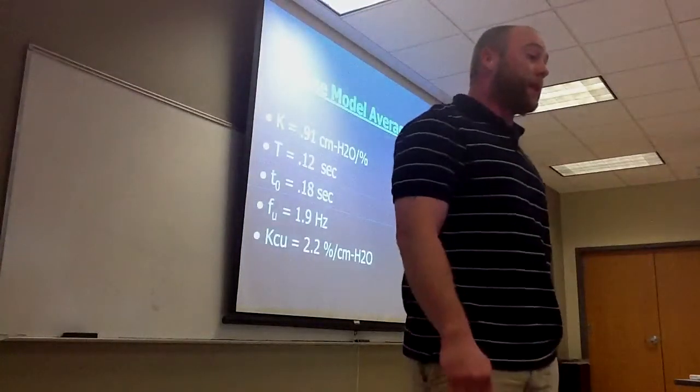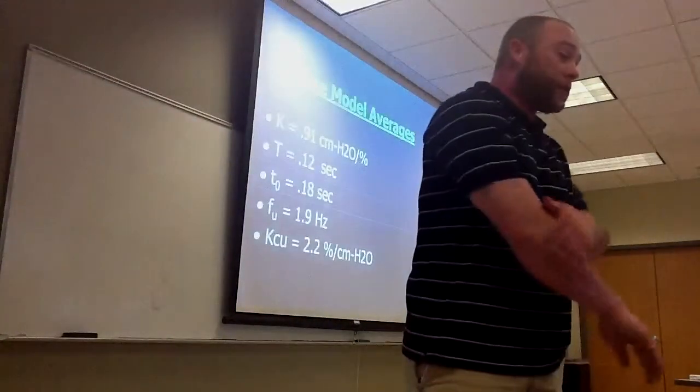and then the averages of our sine: our gain was 0.91, our time constant 0.12, our dead time 0.18 seconds, FU of 1.9 hertz, and a KCU of 2.2 percent over centimeters of water.